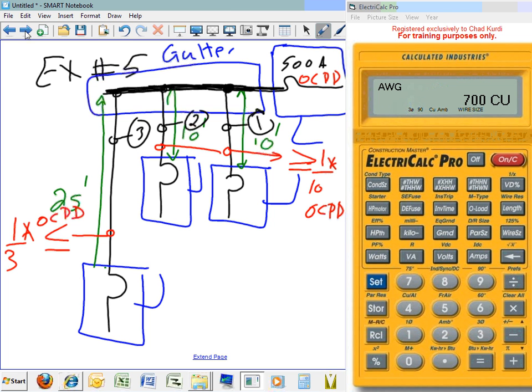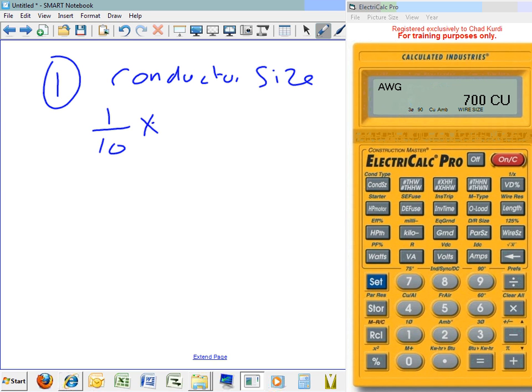Okay, so let's start with number 1. So number 1, as you can see, conductor size. It says 1/10 times the overcurrent device, which is 500. What would that give you? 50 amps, right? The minimum conductor is 50 amps. Okay, cool.